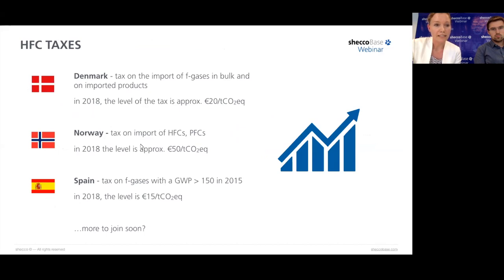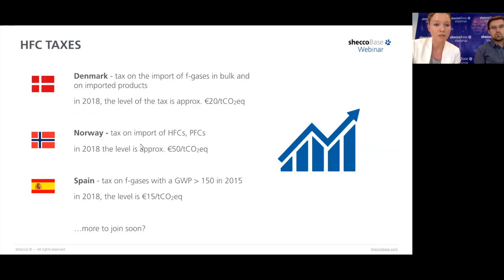Some countries have decided to introduce HFC taxes to increase the price of HFCs and motivate companies and end users to invest in alternative technologies. The level and application of tax differ from country to country. The levels vary between 15 euros per ton of CO2 equivalent up to 50 euros per ton of CO2 equivalent, which is the case in Norway. Some other countries are also considering introducing this tax, so we may see more joining this or next year.